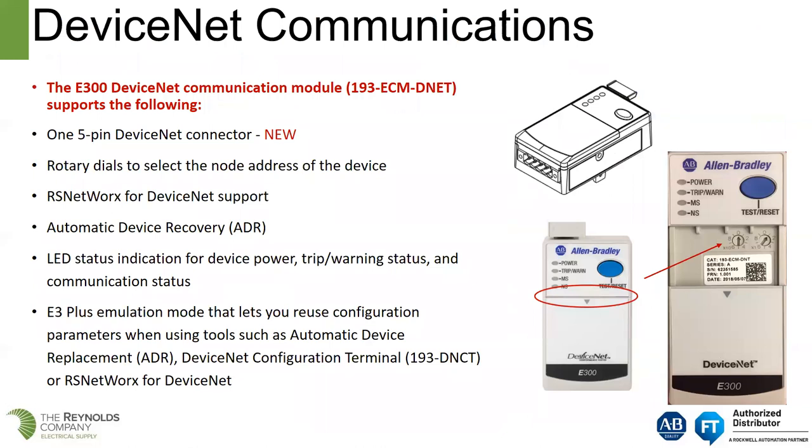For DeviceNet communications — for customers still using DeviceNet MCCs — we do have a DeviceNet adapter for the E300. It uses RSNetWorx for DeviceNet support, and you can still use ADR. So if you have E3 Pluses on a DeviceNet network being reprogrammed with ADR, we can still do that. With the E300, we can actually put it in emulation mode, which will emulate the E3 Plus overload relay and let you reuse the configuration parameters.